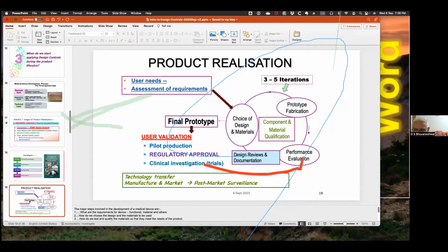And the same thing applies to all other countries, whether it's Australia, Canada, China, Japan is also very strict. Korea, even South Korea has a lot of strict requirements. So every country, you will need to have their license or approval before you can market a medical device in that country. That goes internationally. There's no saying that, okay, you have a CE mark and it's approved in Europe, you can market in the US, or even Korea may not sometimes accept it.